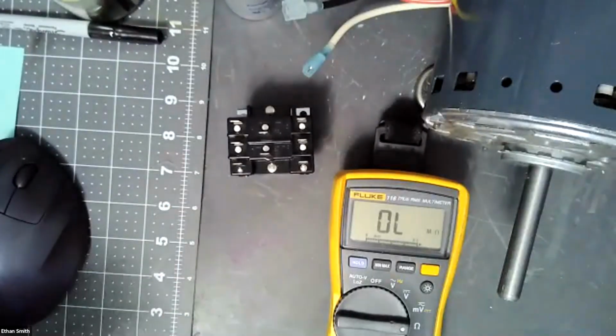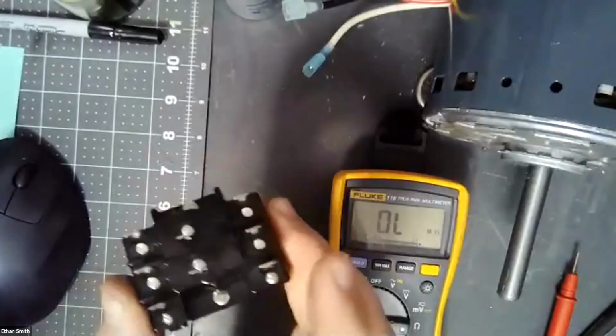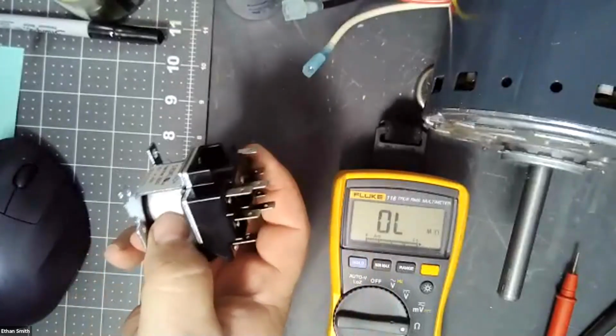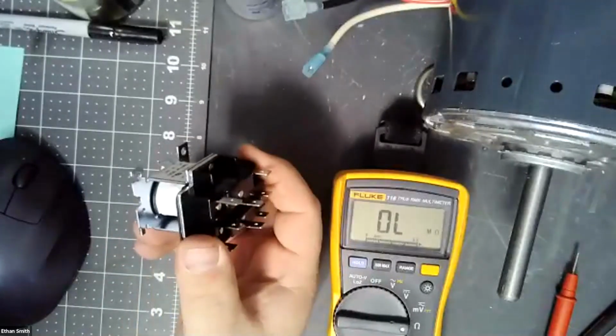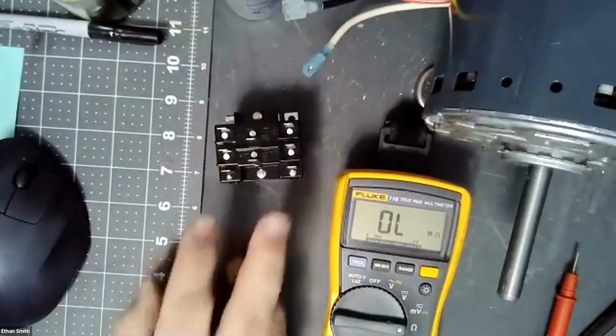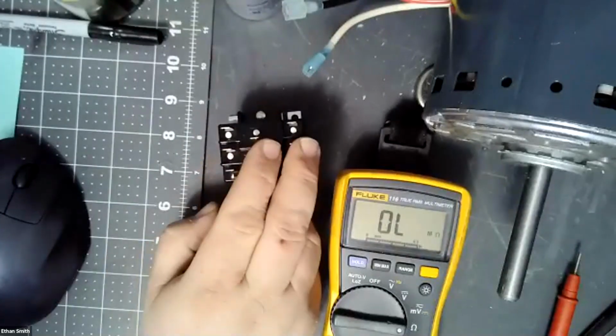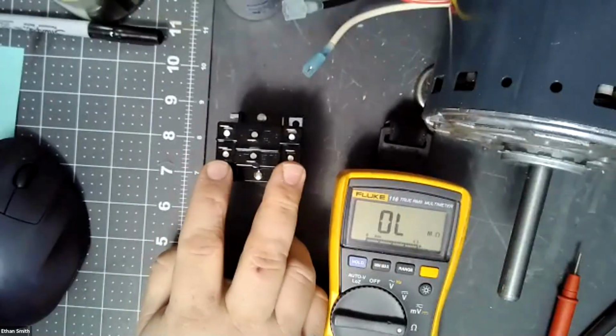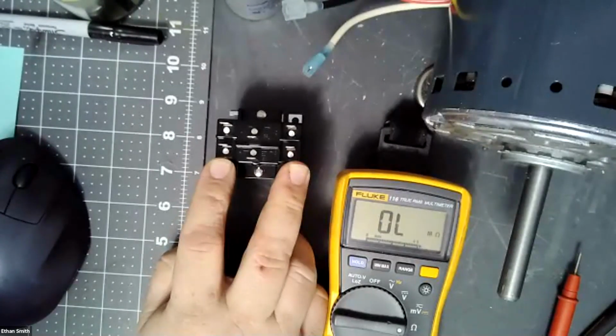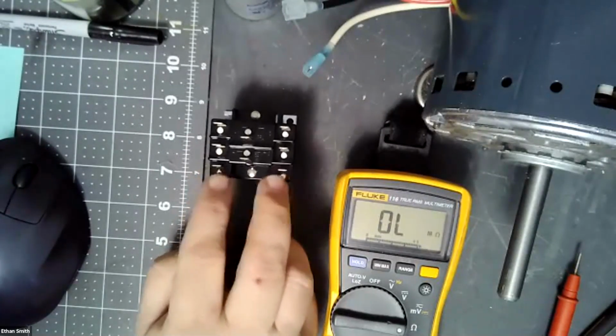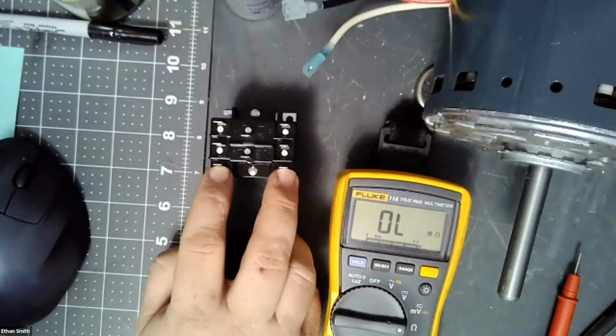Okay. So most 24-volt coils on residential equipment are going to read between 10 and 20 ohms, depending on how big of a contactor they are. That coil is going to change size. Rooftop units, typically their contactors are around 15 ohms. Okay, but that's kind of how we're going to test coils. So we can test the contacts really easily, just open or closed, voltage across them, or we can ohm across them. Coils are the same thing. Coil under load is going to have a voltage drop across it because it is a resistive load. And when it's unloaded, we want to take a resistance reading through it.